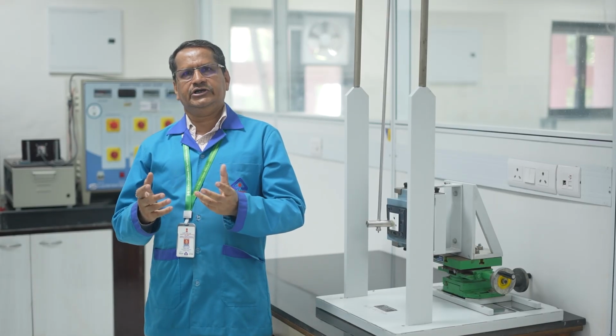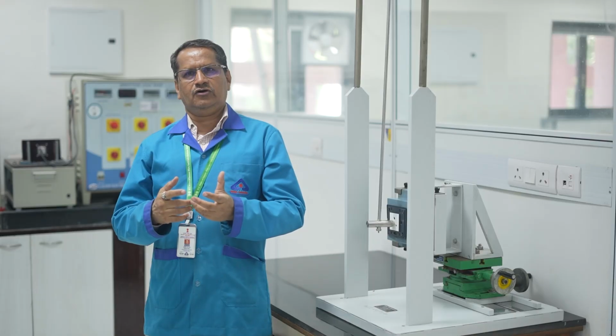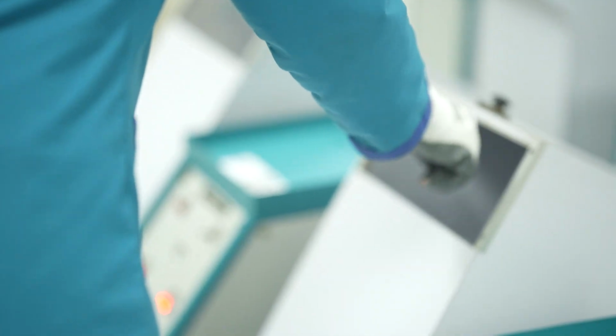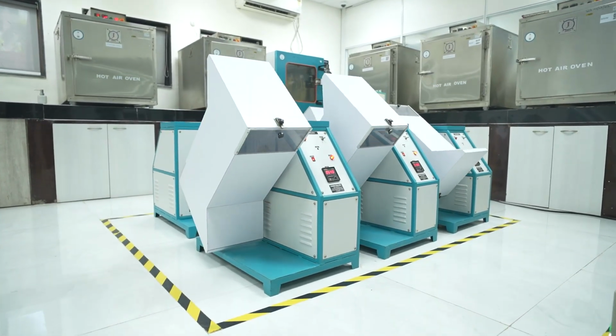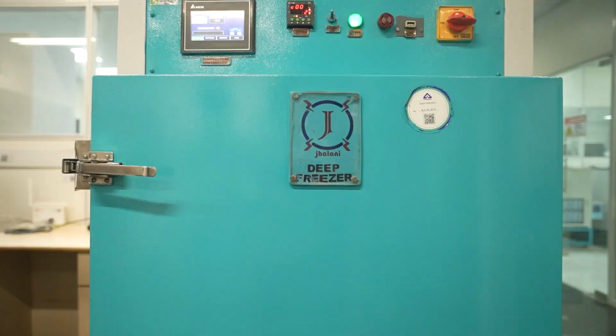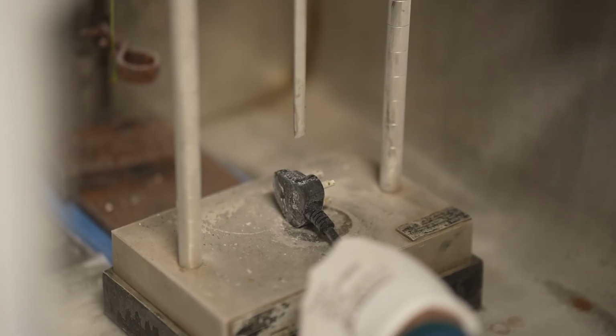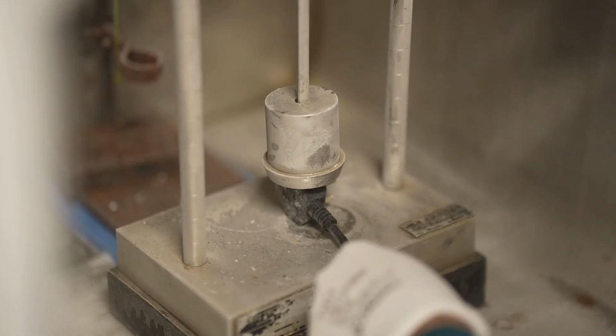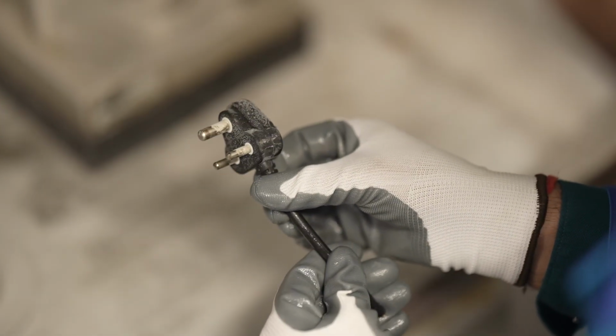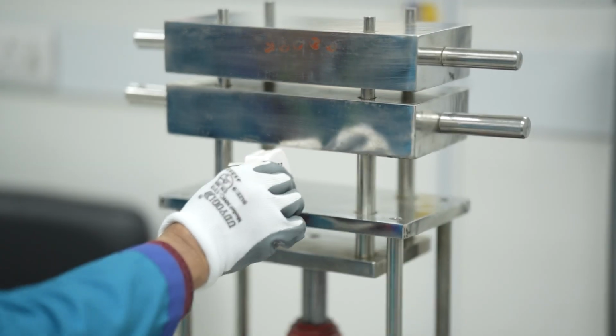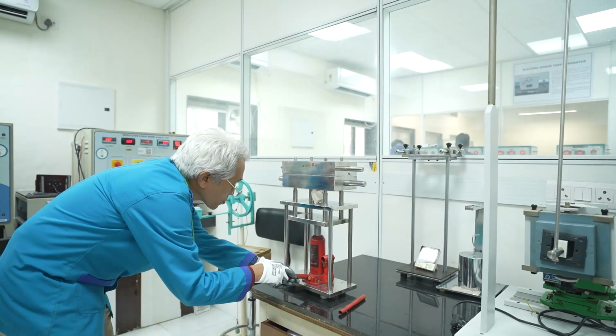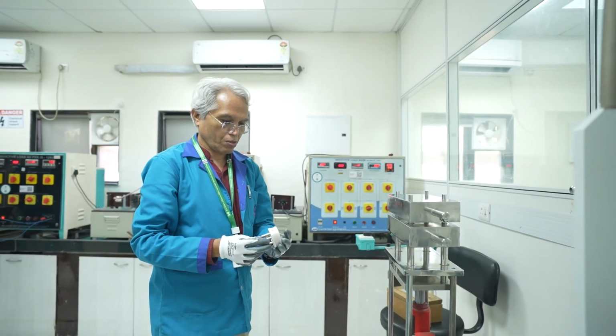Mechanical strength test. Clause 24. Plugs and sockets are required to withstand mechanical stress. The impact test on fixed socket outlets is performed by applying specified blows to assess their durability. Portable accessories are placed in a tumbling barrel and subjected to a specified number of drops as outlined in the standard. Subsequently, these accessories undergo an impact test with a specified force after being conditioned for 16 hours at -15 degrees Celsius. Compression tests of 300 Newton are applied for 1 minute to verify their ability to remain intact under pressure.